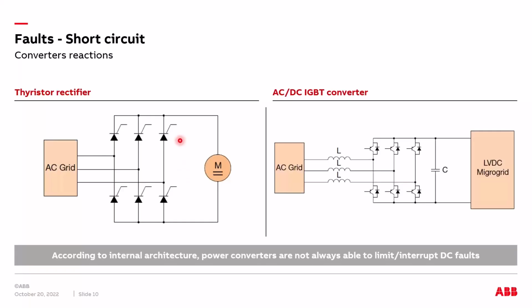Inside the thyristor, we cannot change the current, so the only way is to change the voltage polarity. But we cannot change the voltage polarity inside the DC system, because if we have loads or battery systems or any local generation, by changing the voltage polarity, we can create very big issues on our system, and in some cases also a very dangerous short circuit, for example, if we have batteries applied to our system.